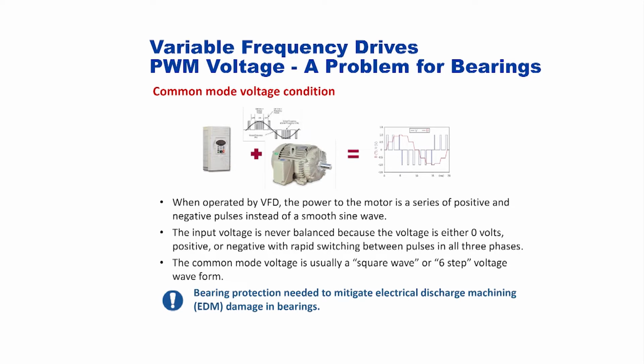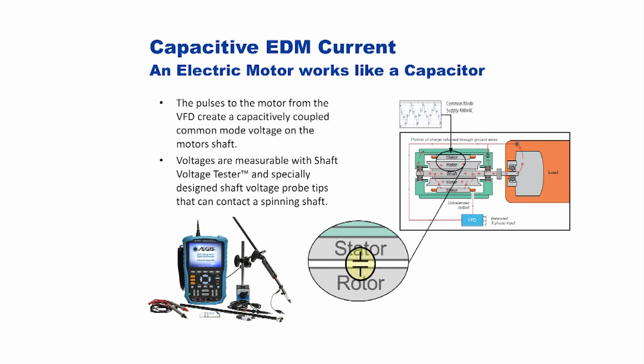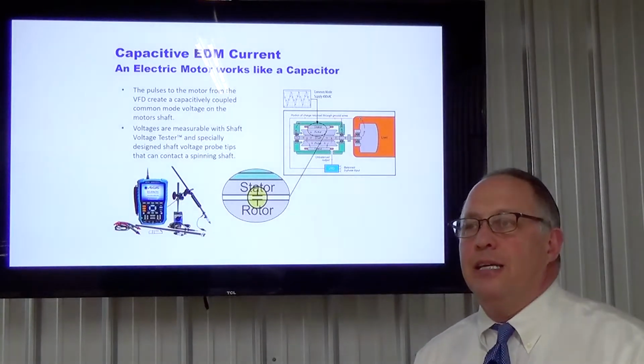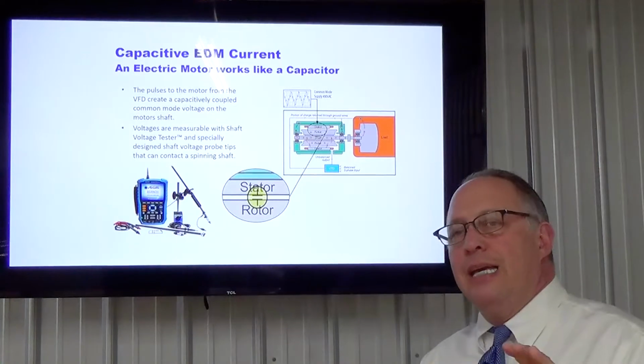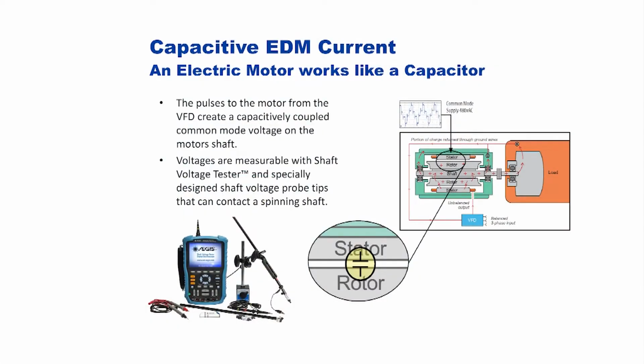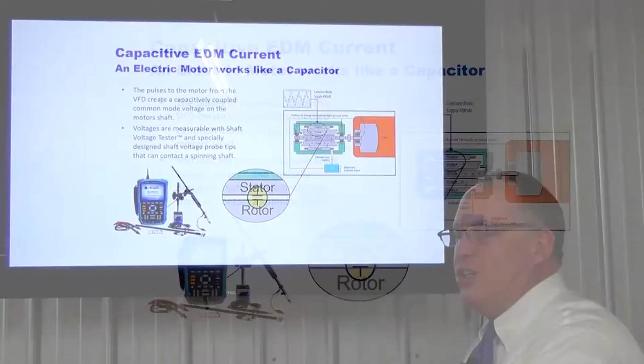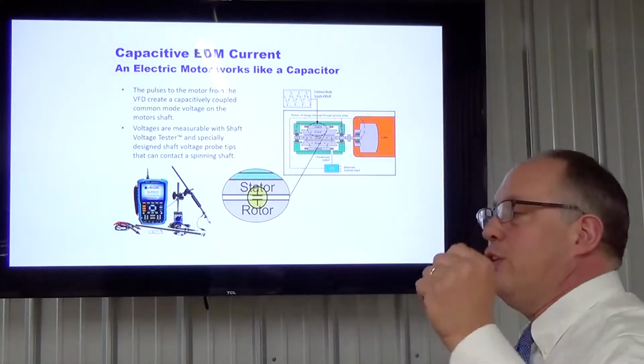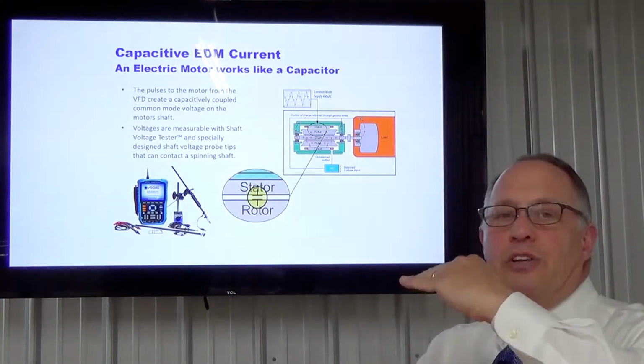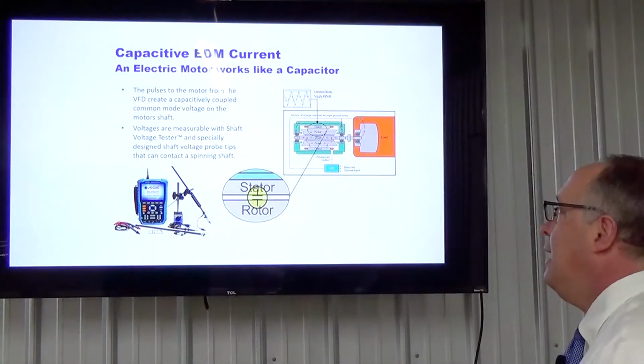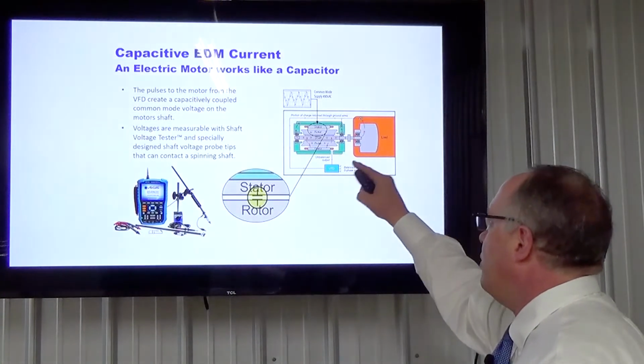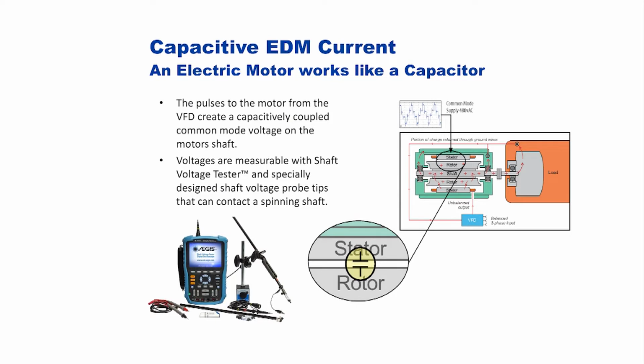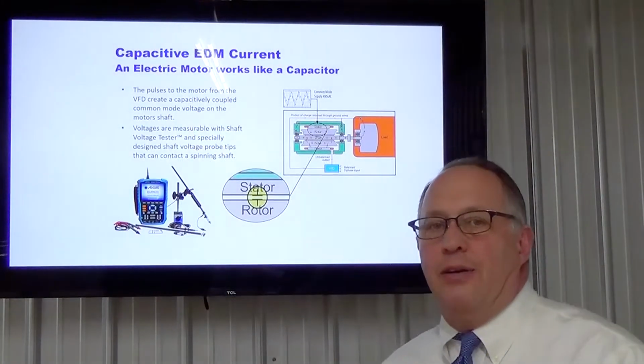Bearing protection is needed to mitigate electrical discharge machining damage in these bearings. Capacitive EDM current: an electric motor works like a capacitor. This is the issue. How does the voltage get induced to the shaft? Well, the pulses to the motor from the VFD create a capacitively coupled common mode voltage on the motor shaft. In other words, we've got a shaft just sitting there, and then we've got the rotor and the stator, which between them, when not matched properly, will produce a capacitive voltage, and that voltage gets induced onto the shaft itself. Voltages are measurable with a shaft voltage tester and specially designed shaft voltage probes that can make contact with the spinning shaft.